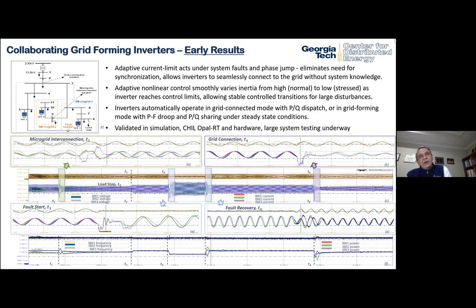So inverters typically operate trying to present high inertia on the system so that they are suppressing any dynamics and things that are happening. And then when you end up getting a situation where the inverters are near the edge of their control, the inertia automatically goes low and allows that inverter to do a phase jump.